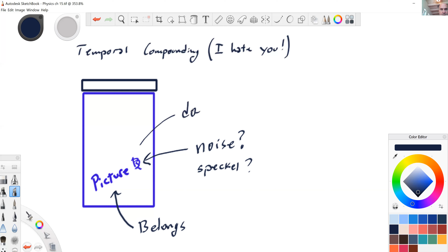So temporal compounding is a good way of, once again, reducing noise, reducing speckle. In words, from the history from earlier frames, a smoother image with reduced noise, higher signal to noise ratio, and improved image quality is produced. The primary limitation of temporal compounding is frame rate, or at least the perceived frame rate. The frames are actually being created at the correct speed, but we're seeing all this previous information, and it can be difficult to watch during a Doppler.